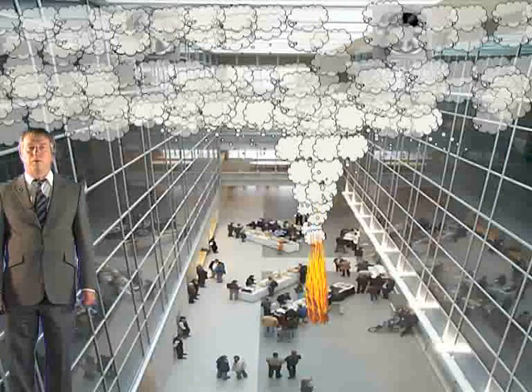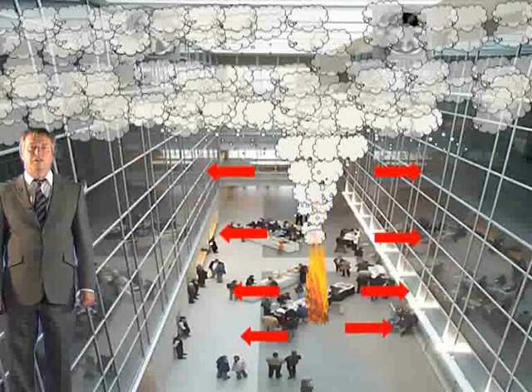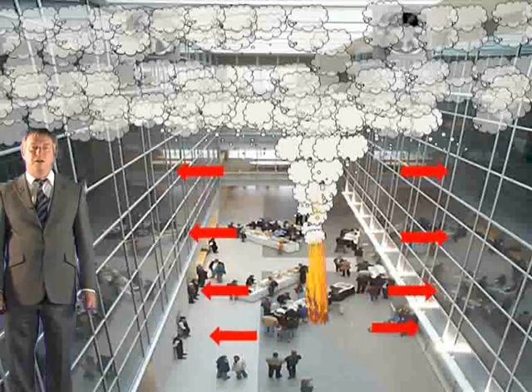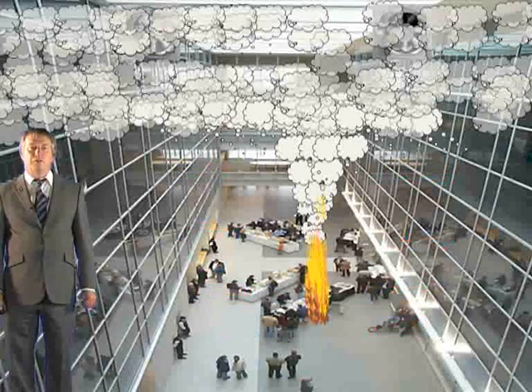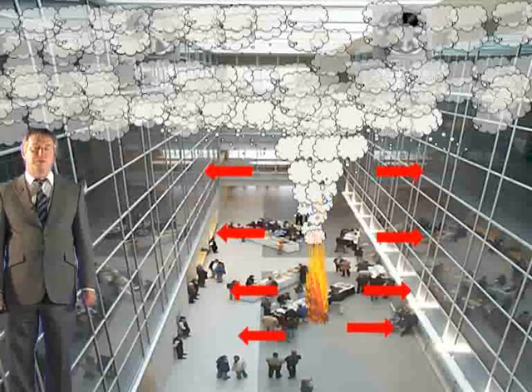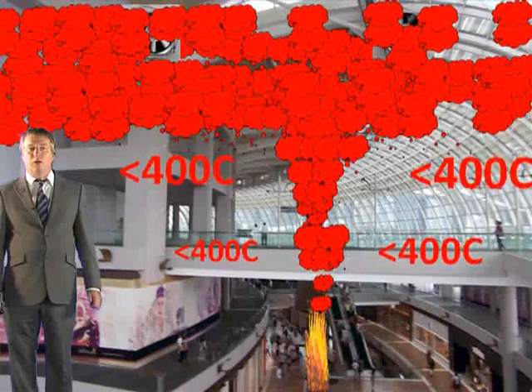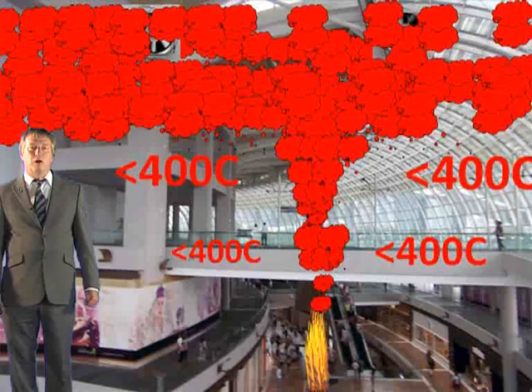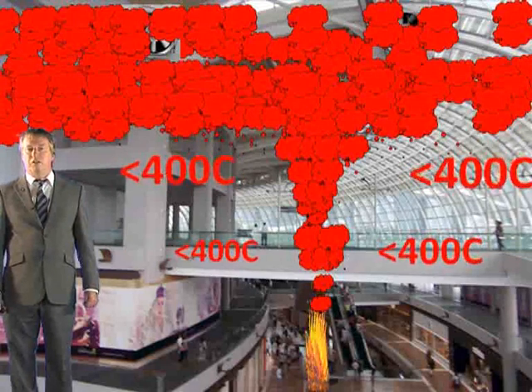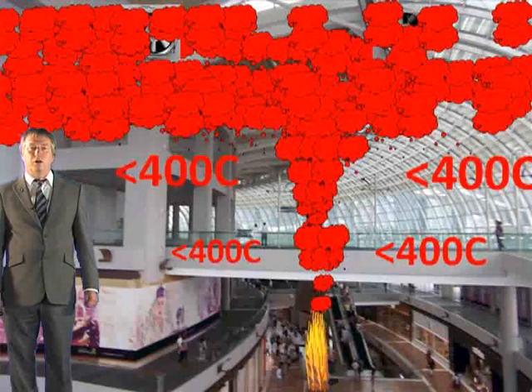A typical example is where an atrium facade has glazing which is not fire resisting, but which is known to be able to survive gas temperatures up to some specified value. Another example was in an airport where the structural steel did not require the usual 2-hour fire resistance protection because it was demonstrated that the smoke temperature would not exceed 400 degrees Celsius.